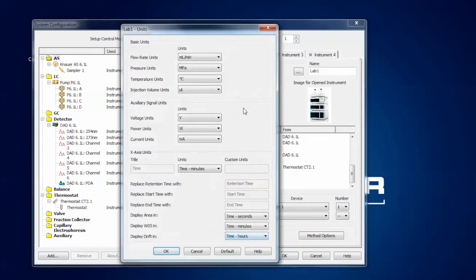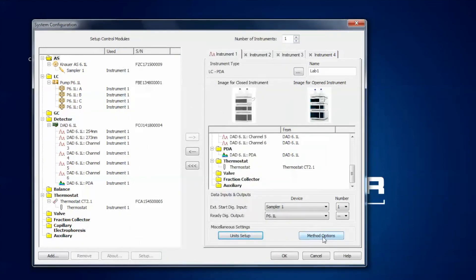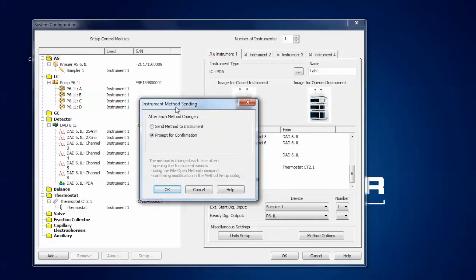In the configuration window you can also change the unit setup — it gives you an overview of the used units and you can adjust temperature, flow rate, pressure, injection volume and more. Much more important is the method options setting, which defines when a method is sent to the instrument. The method is changed each time after an instrument is opened, an existing method is opened, or when you confirm a modification in the method setup. You can decide whether sending the method should be confirmed by the user beforehand or sent immediately without asking. I will leave it set to prompt for confirmation.